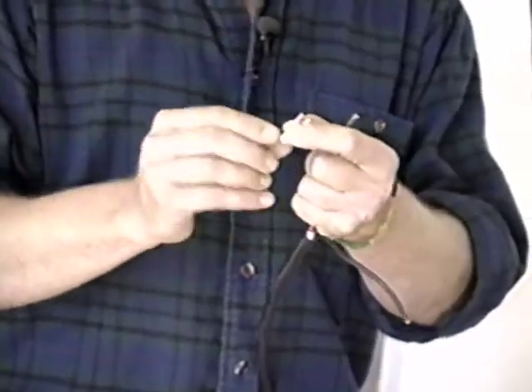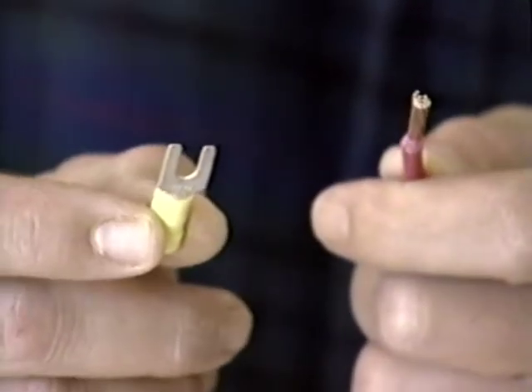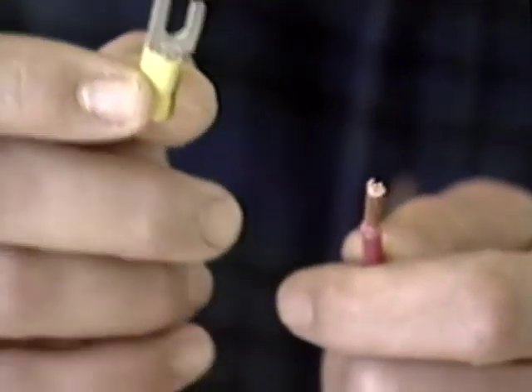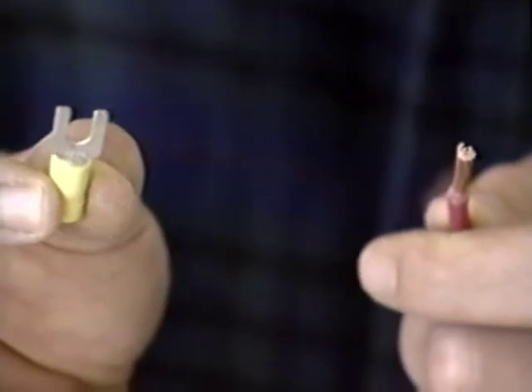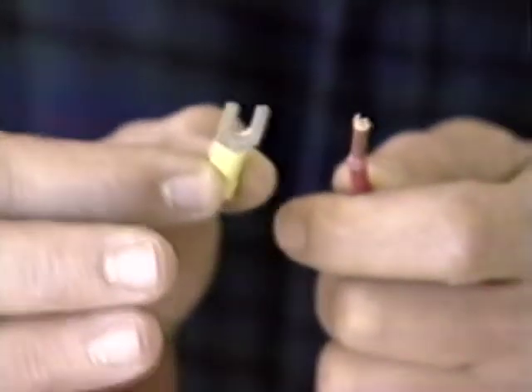Having the right tool to strip number 10 wire properly, without damaging any of the copper strands, is real important. Likewise, having the proper connector to go onto that wire is real important. This is a number 10 spade terminal, the recommended connector for this particular photovoltaic module and this particular wire.